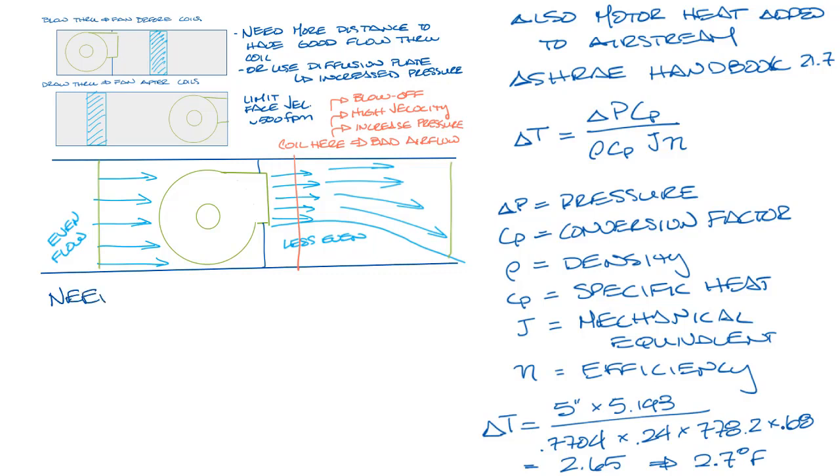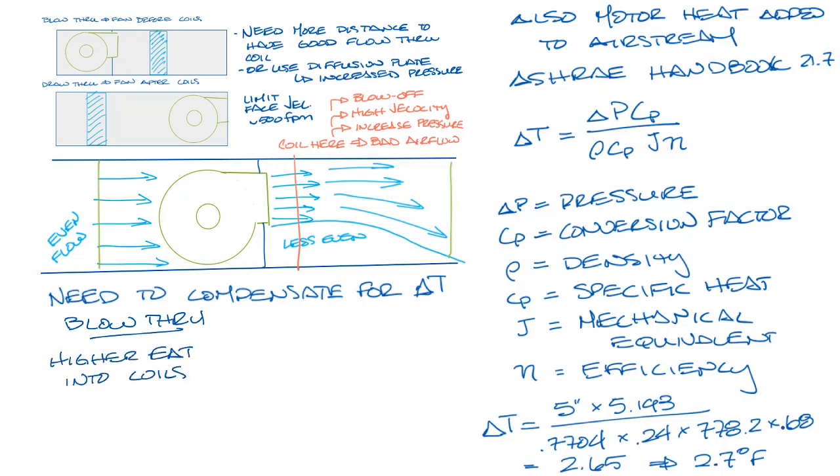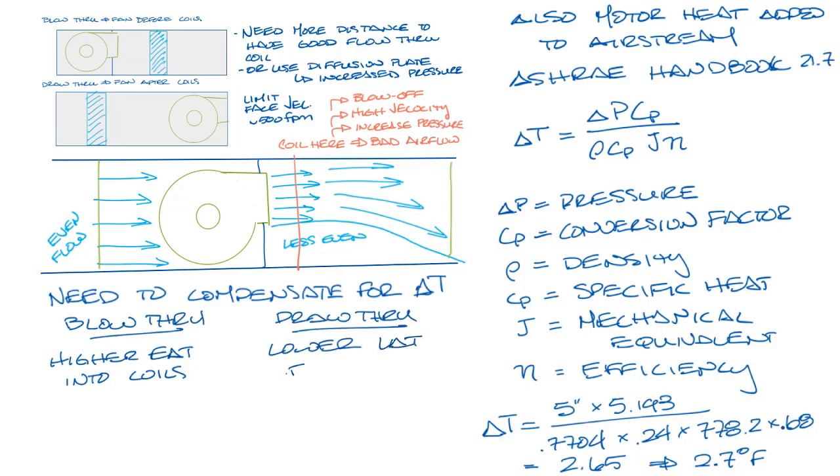So you are going to need to compensate for this motor heat in your system somehow. If you have a blow through arrangement, then this extra heat will be entering the coils. So you'll have a higher entering air temperature into the coils. In a draw through arrangement, you will have to lower your leaving air temperature from your coils because the heat will be added after the coil.